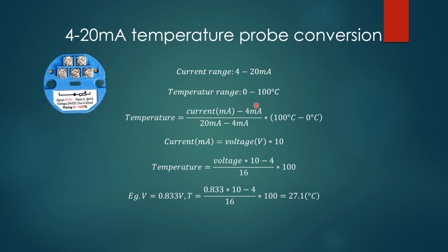Then minus 4, because your current starts at 4. And then divide by 16, because your range of current is always 16 milliamps apart in a 4 to 20 milliamp loop. Then you multiply by 100 to rescale your current into temperature. Here's an example. If your voltage readout is 0.833 volts, you multiply by 10, and this is your current now. Then current minus 4 tells you how far you are from the starting current. You divide by 16 to get where you are within the 16 milliamp range, and then multiply by 100 to turn this into temperature. So you're at 27.1 degrees C.